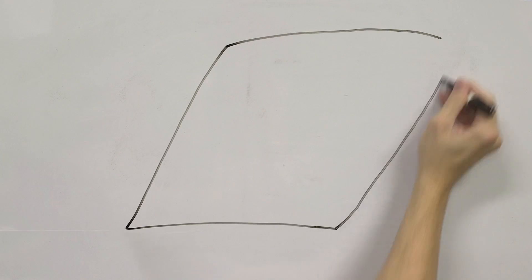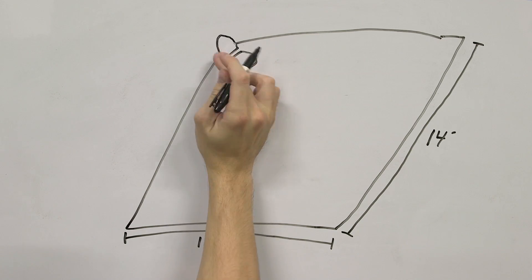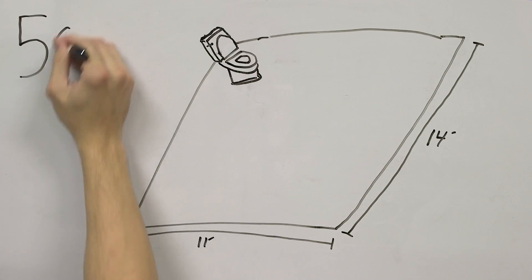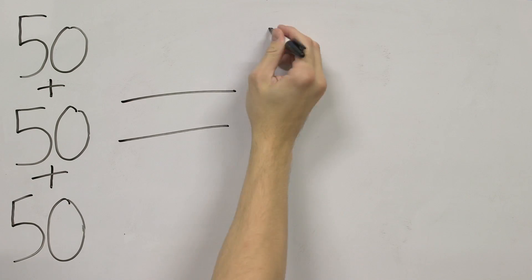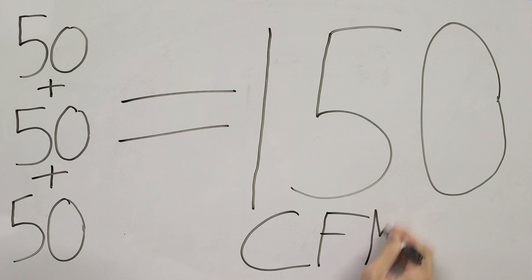A bathroom that is 11 foot by 14 foot would need to be sized by fixtures. This example bathroom has 1 toilet, 1 shower, and 1 tub, which would equal 150 CFM, and you would need a fan of 150 CFM or above.